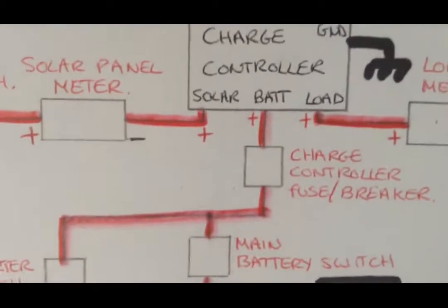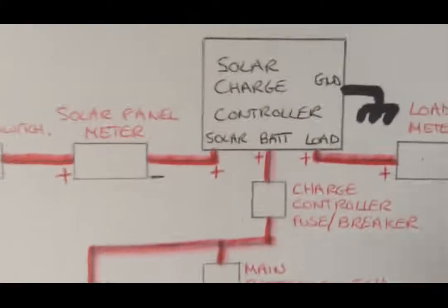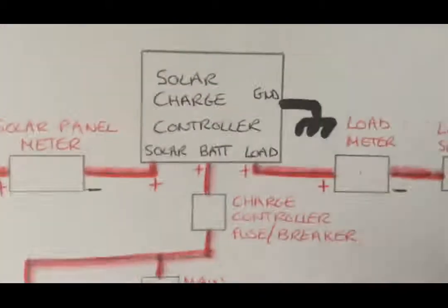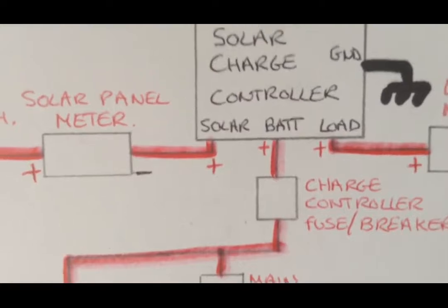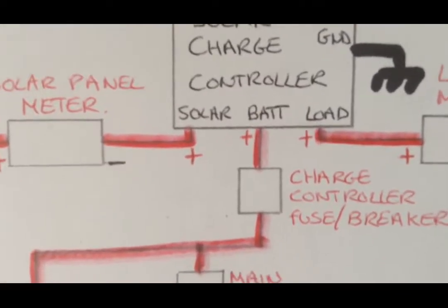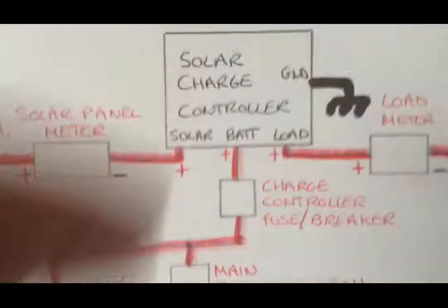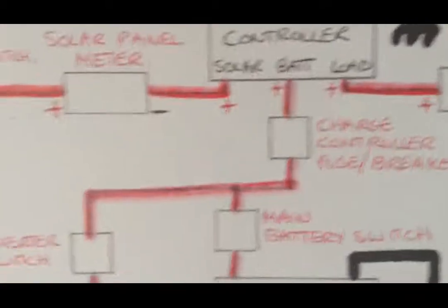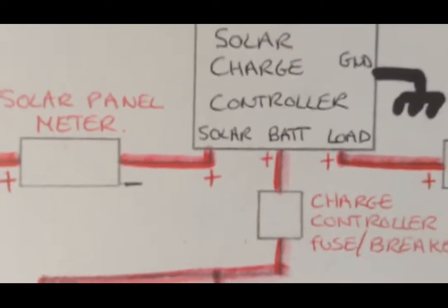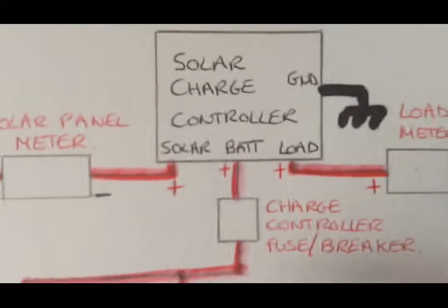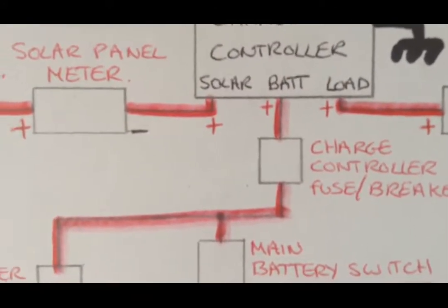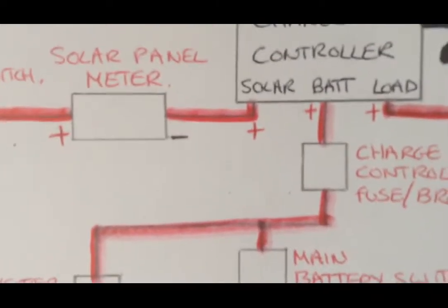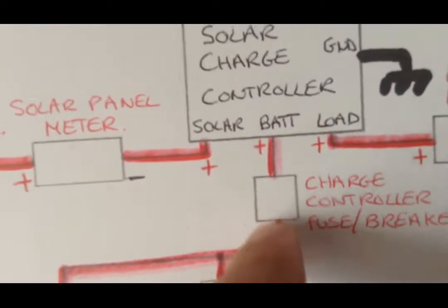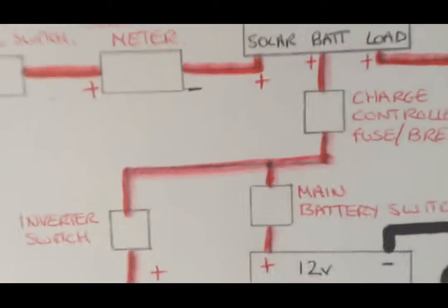Right, so we dealt with the solar input, we will deal with the battery. On your charge controller there's a pair of terminals marked battery, or it might just have a battery symbol on it. The plus wire from the charge controller needs to go to a fuse. A fuse you can wire either way round, and the breaker has to be wired a particular way. Now in this case, the plus of the breaker must be wired towards the plus of the battery.